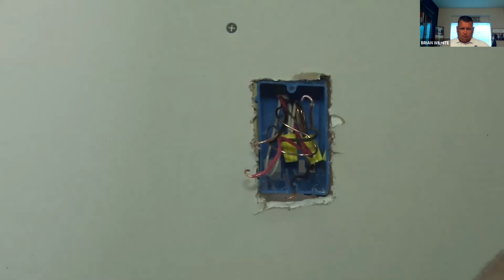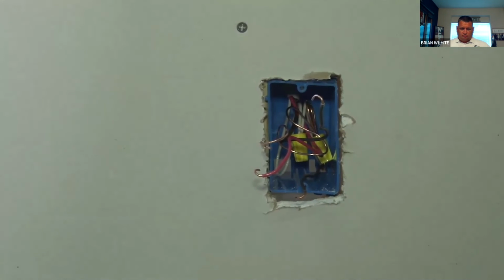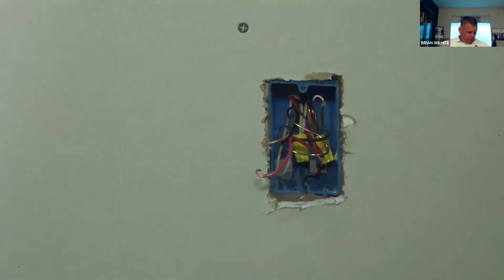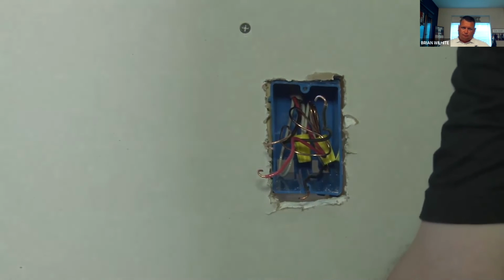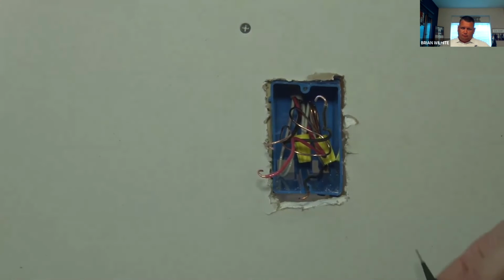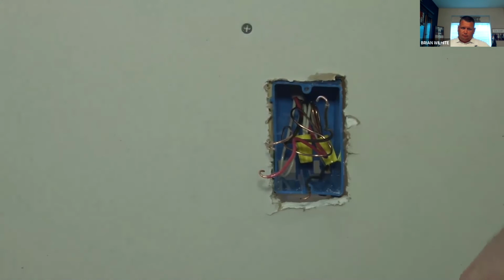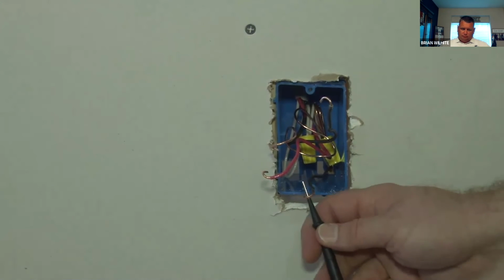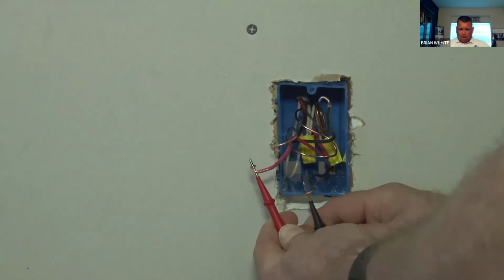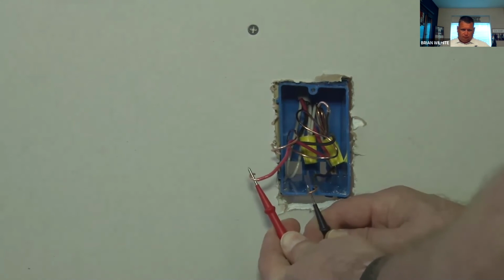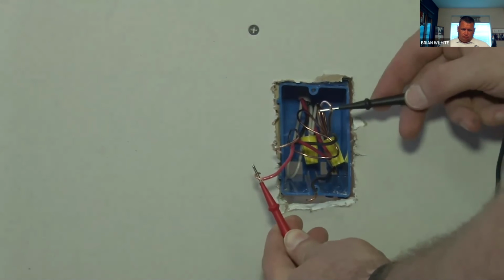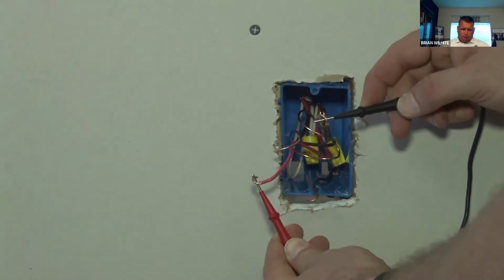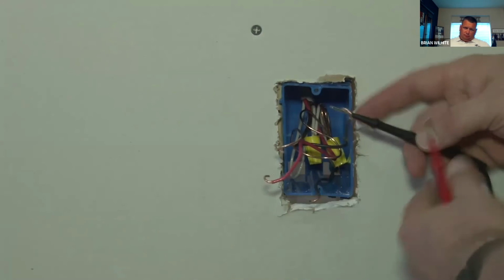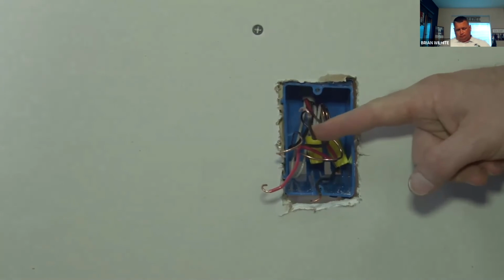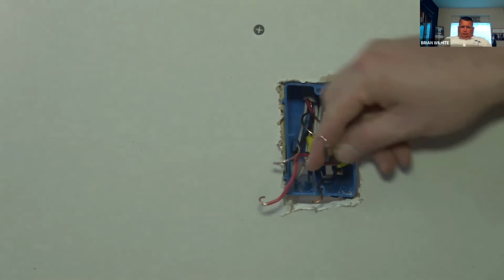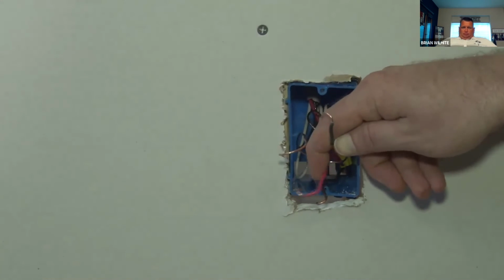The next step is, since we've got that first box, two wires connected, I'm going to take my meter and change it to the continuity setting. When I'm testing for continuity, what I'm looking for is an electrical connection between any two of these wires. So I pick any two of the wires and test it. In between these two, I do not have continuity. And yet when I move to this one, I do. What that tells me is that this red wire and this black wire are the runners in between the two boxes. Now I know how to connect my switches up.